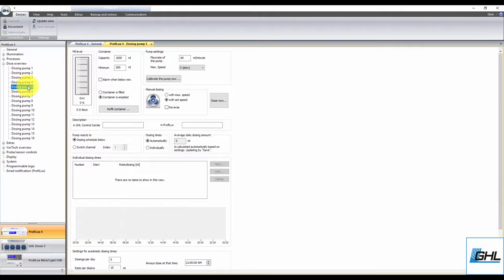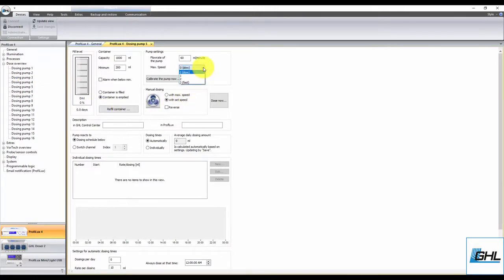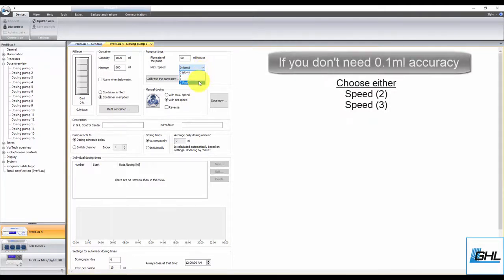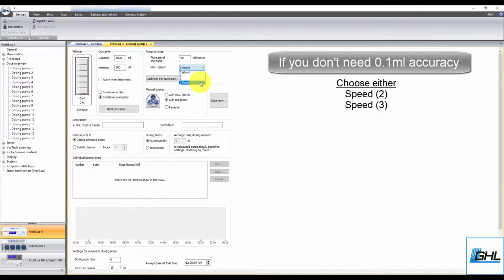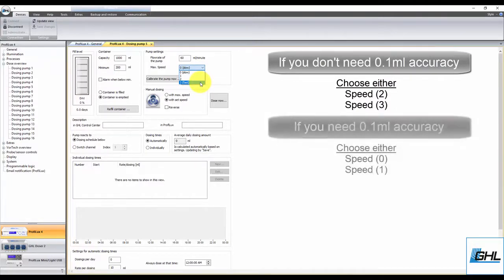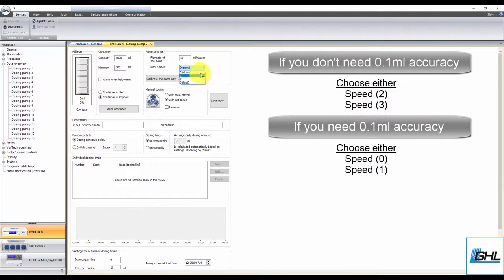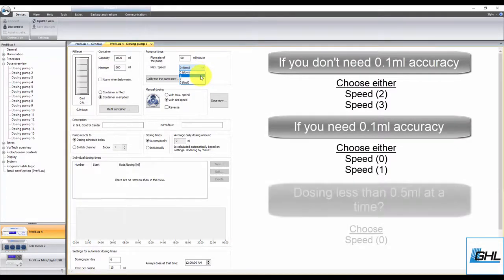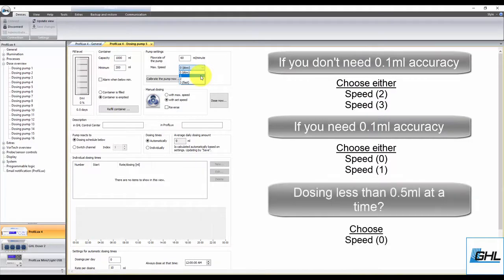From here, choose at what speed you want to run the pump at. If you'll be dosing fluids that do not require 0.1 milliliter accuracy, speed 2 and 3 will suffice. If you need to dose with 0.1 milliliter accuracy, set the pump speed to 0 or 1. If your single dosage amounts are going to be less than 0.5 milliliters, we recommend you select speed 0.